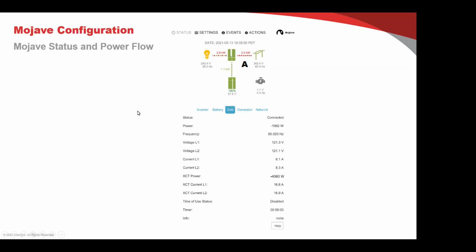Okay, thanks, Bill. So after you've done the configuration, you hit the status tab up here, and then you can look at status, inverter, battery, grid, and so on. Here we're showing the grid and the power flow diagram. Energy coming up from batteries, the green dots going to the load, is being blended with power from the grid, the red dots. Notice that there's current coming in. We're using our external CT, so kind of a self-consumption thing going on here. So you've got full power, frequency, voltage, and current on L1 and L2, external CT currents, and time of use status. It's all right there, a very easy to use interface.